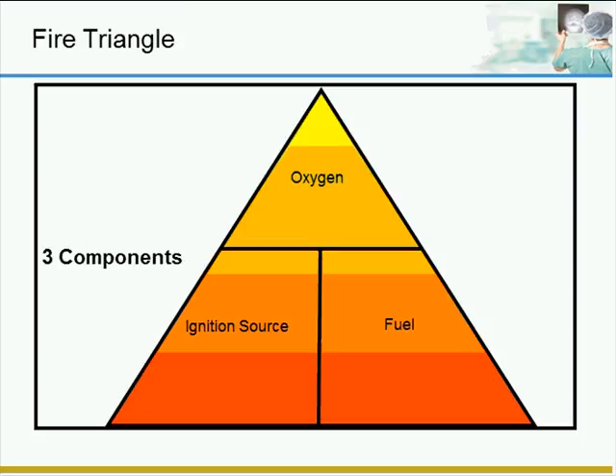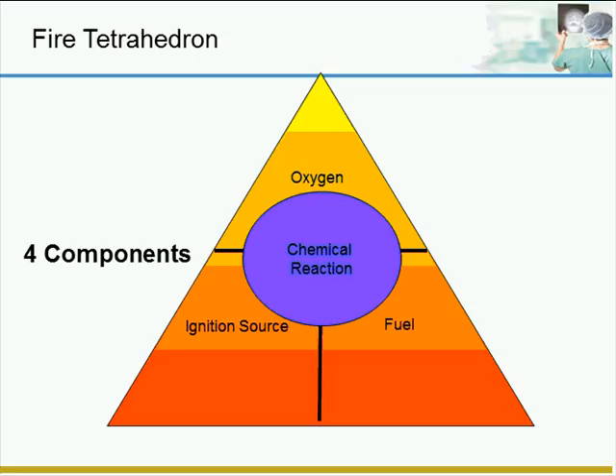This slide represents the classic fire triangle. You cannot have a fire without these three components: oxygen, ignition source, and fuel. This is the fire tetrahedron. This was introduced with the introduction of Halon 1301. Halon 1301 is no longer available. It was a clean agent used in sensitive areas for fire suppression. It is no longer available, but other clean agents such as FM200 are now available. Clean agents break the chemical reaction within a fire.